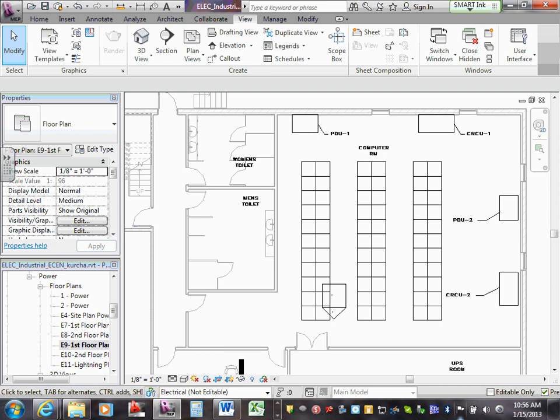We can go with a smoke detector. So with the smoke detectors, you're going to have your system come in here. The first one is 9 feet, so you're going to 4.5 by 4.5. There's going to be your first. Again, another 9 feet. These are your smoke detectors going all the way across. What you're doing is gridding them at 9 feet on center, and half of that from the wall. Makes sense? Like we did with lights. This should give you a good idea. So there'll be a lot of smoke detectors, and these are the underfloor ones, right? The underfloor.